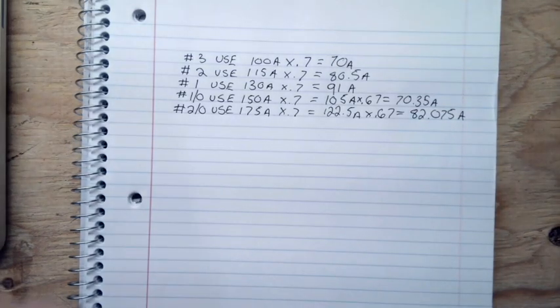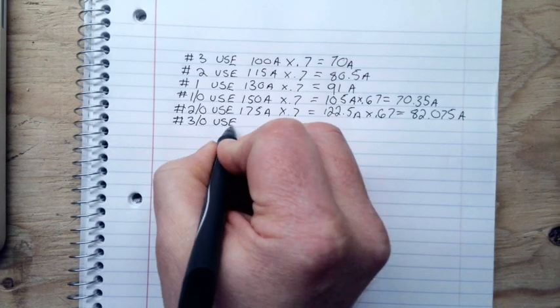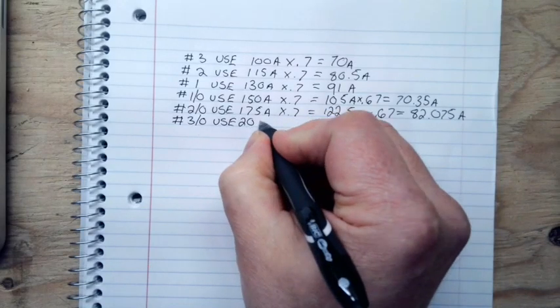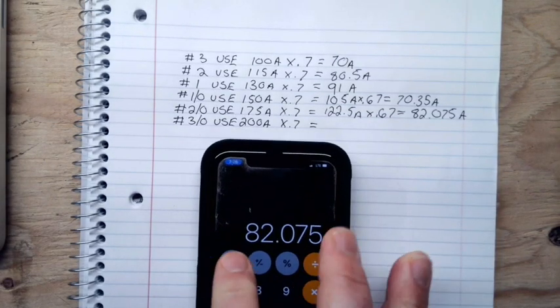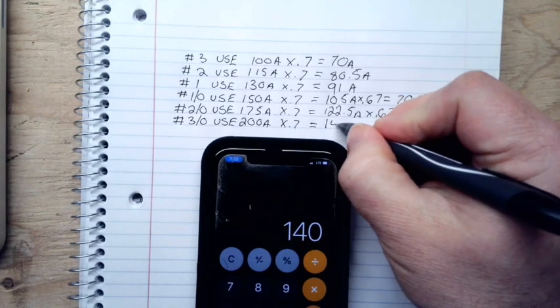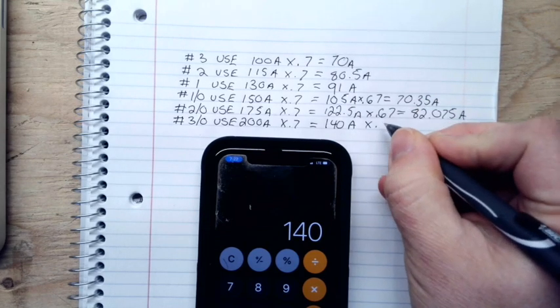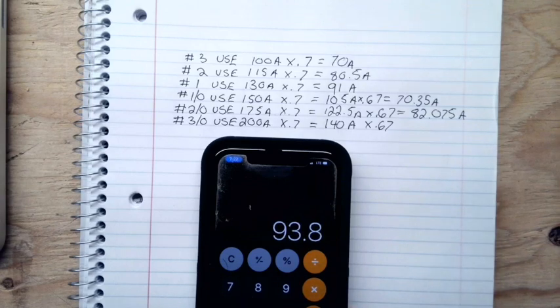So now I've got to go to our number three ought U.S.E. And it says here that number three ought is good to 200 amps. It's quite a jump. 200 amps times 0.7 is equal to... 200 times 0.7 equals 140 amps. All right, again, we know that that's good enough to correct for the adjustment factor, but will it be enough for the correction factor? Let's see. So now we're going to take that 140 times 0.67 equals 93.8. Still not good enough.